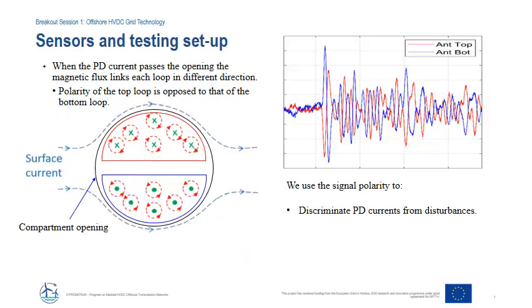Magnetic detection is convenient because the polarity of the output signal can be used for discrimination of PD signals from disturbances. When the PD current passes one compartment opening, the magnetic flux links each loop in a different direction. As a result, the polarity of the top loop is opposed to that of the bottom loop. In addition, providing sufficient noise rejection and amplification of the output signal, the antenna can measure with enough bandwidth as to reasonably estimate the charge of the PD pulse.